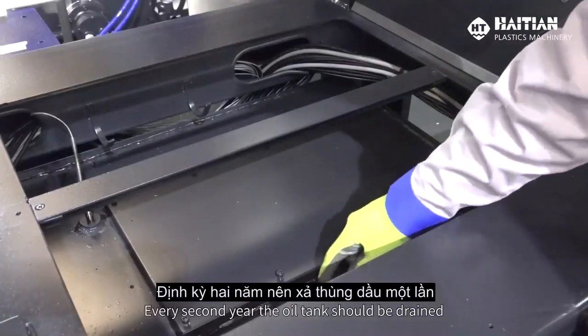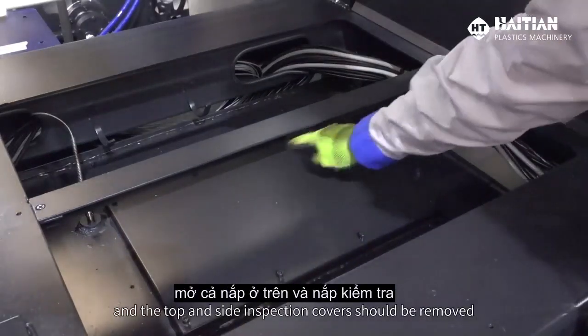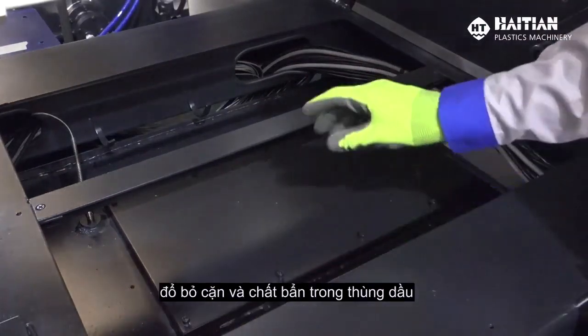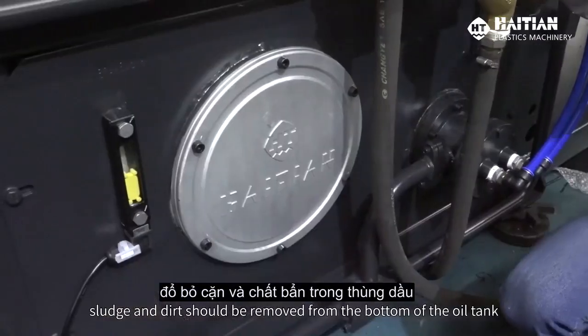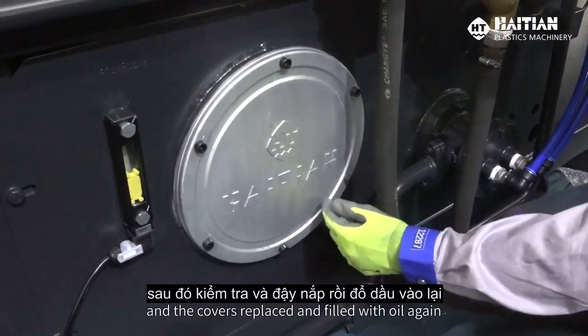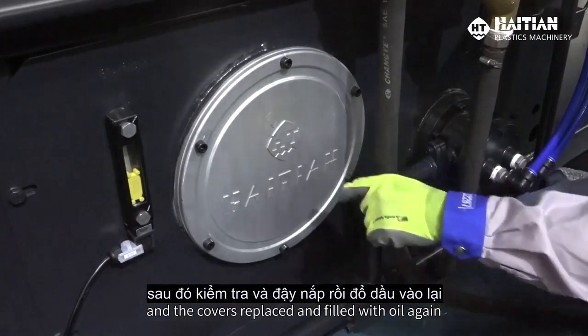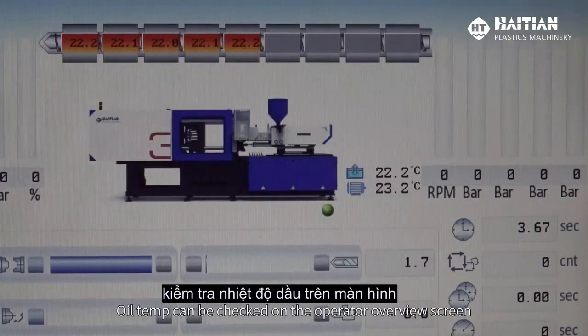Every second year the oil tank should be drained and the top and side inspection covers should be removed. Sludge and dirt should be removed from the bottom of the oil tank and the covers replaced and filled with oil again. Oil temperature check.